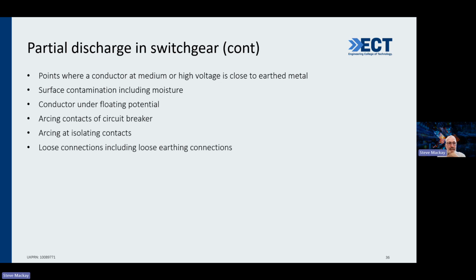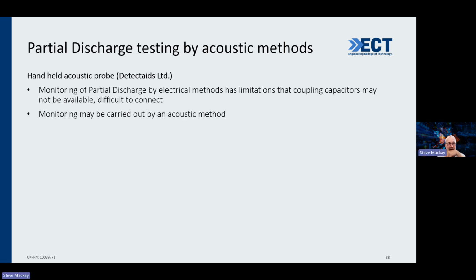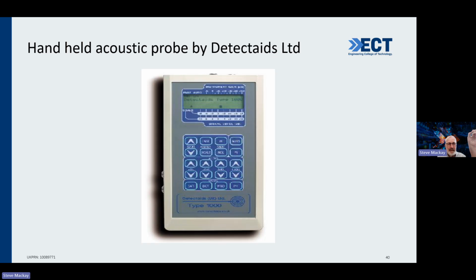In switchgear, obviously surface contamination, including moisture, conductor under floating potential, arcing contacts with the circuit breaker. Loose connections are obviously also a good target. So there's different testing methods here. I'm not going to worry too much about those.